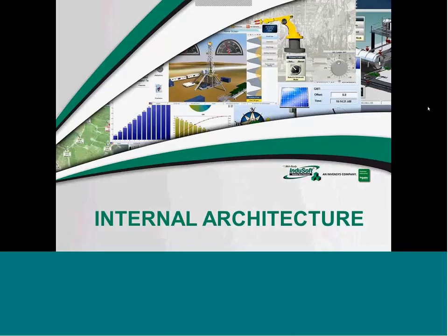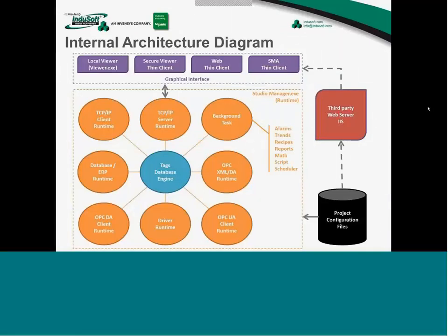With that, just getting started, let's talk a little bit about the internal architecture of InduSoft Web Studio. So in InduSoft, we have two main processes for typical applications. One is called studiomanager.exe, and this is the module that runs in background. So everything that's not the graphical interface runs in this process called studiomanager.exe.